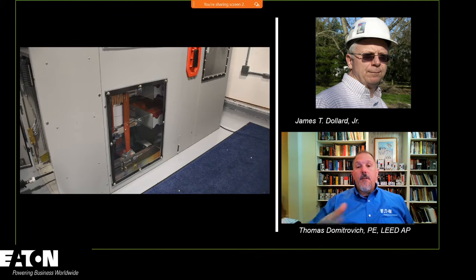And the further up you go, like this is medium voltage equipment, but like you said, there are devices you can fit on the front of a circuit breaker or switches to remotely operate those. I saw one of the chicken switch guys mount that kind of equipment. Most manufacturers will be making stuff like that which goes on the equipment. Either way, you can rack things out, open breakers, close breakers, you can do a lot of that activity remotely.